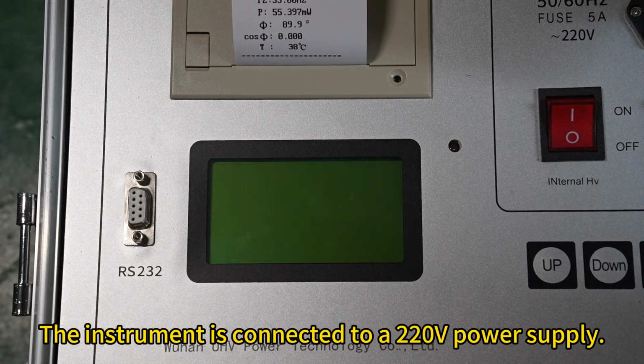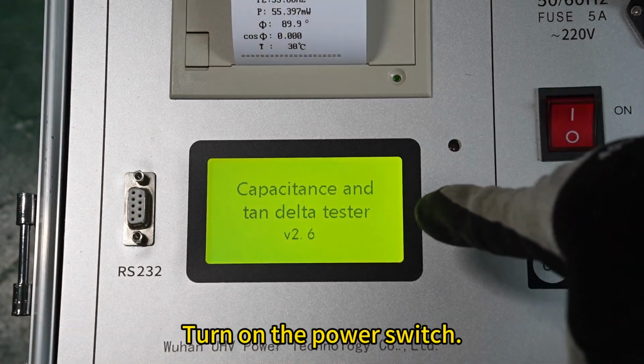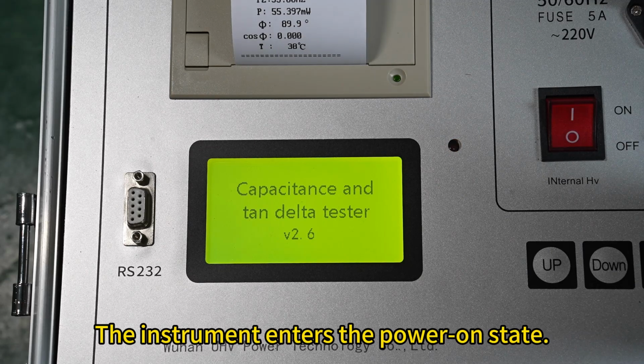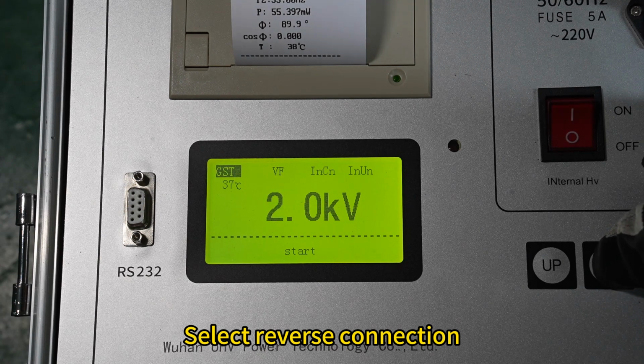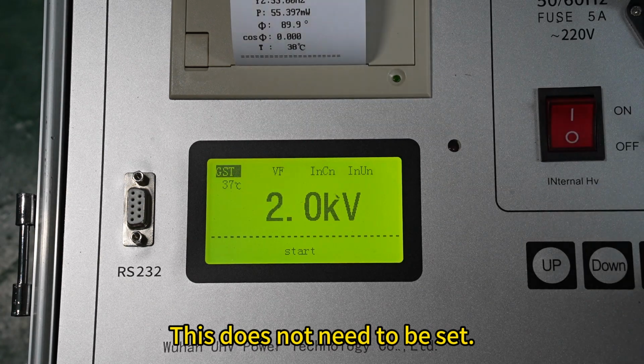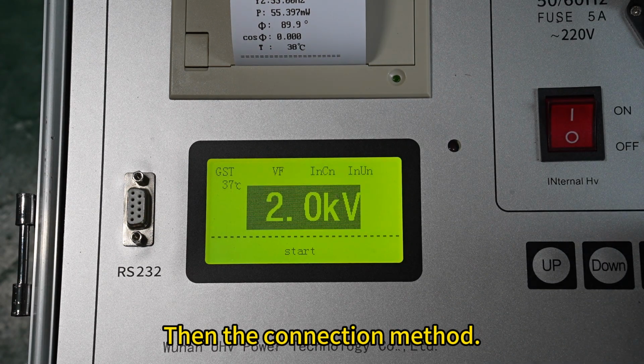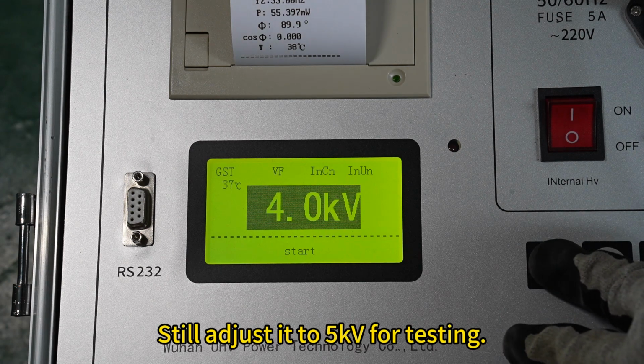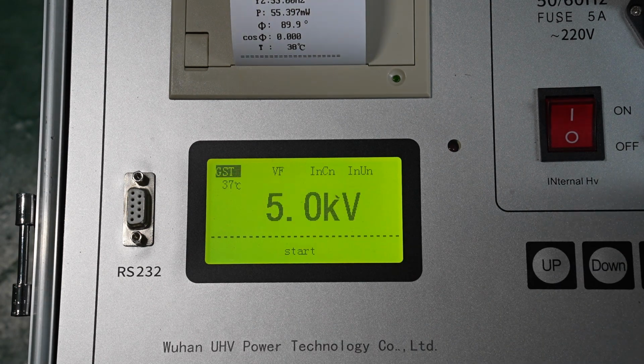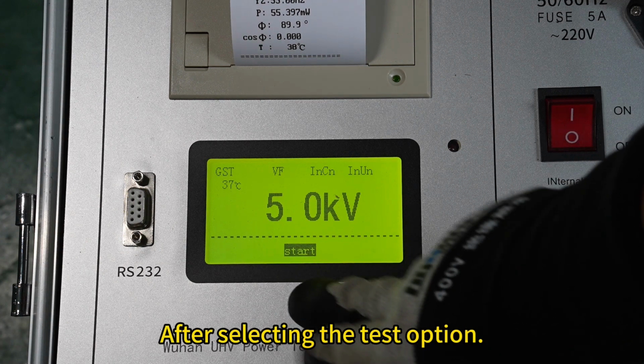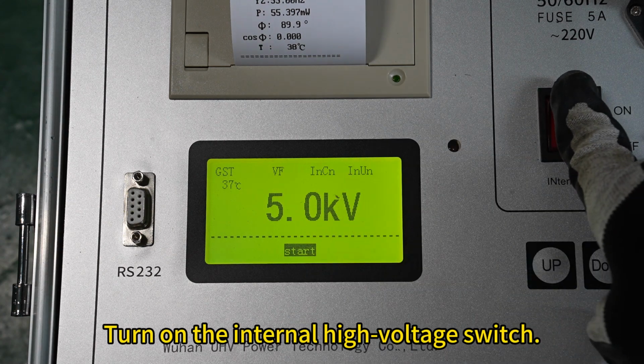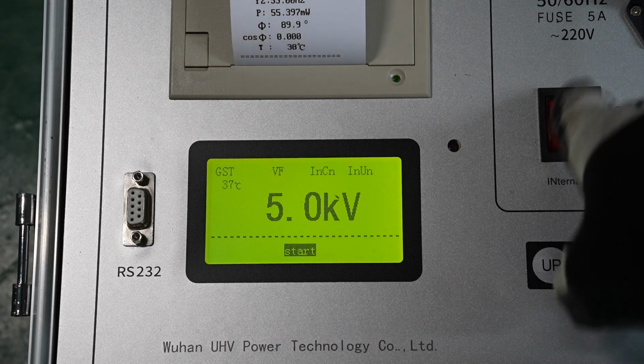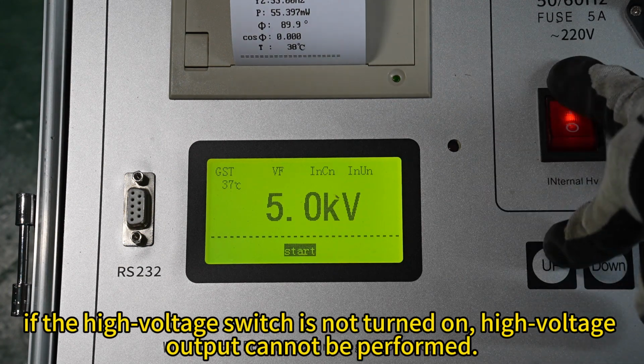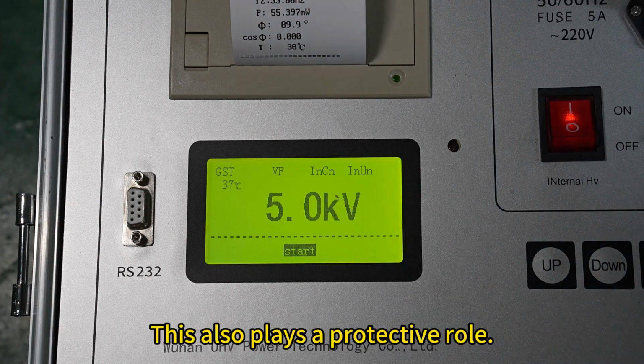The instrument is connected to a 220 volts power supply. Turn on the power switch. The instrument enters the power on state. Here you need to change its connection method. Select reverse connection, GST. This does not need to be set. This is frequency conversion. Then the connection method. Now the voltage is 2 kilovolts, still adjusted to 5 kilovolts for testing. After selecting the test option, turn on the internal high voltage switch. Be sure to note that if the high voltage switch is not turned on, high voltage output cannot be performed. This also plays a protective role.